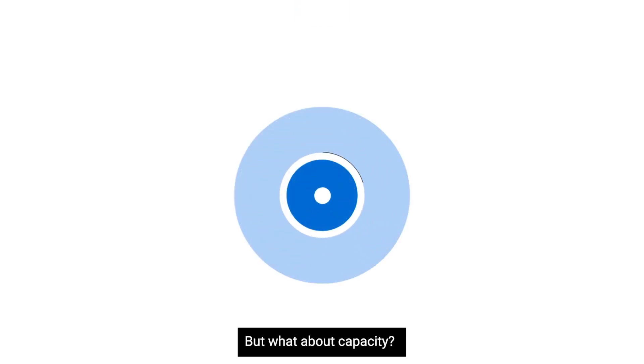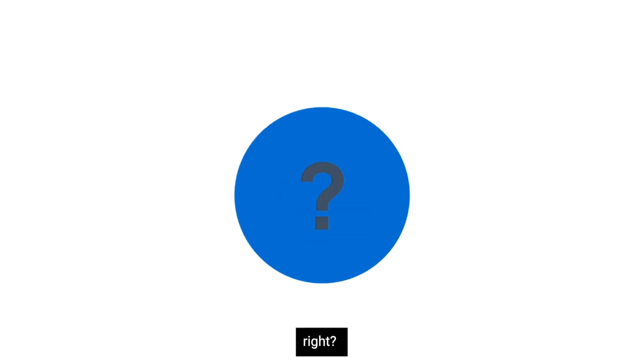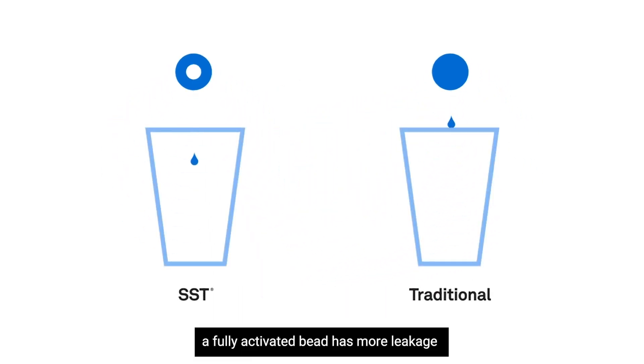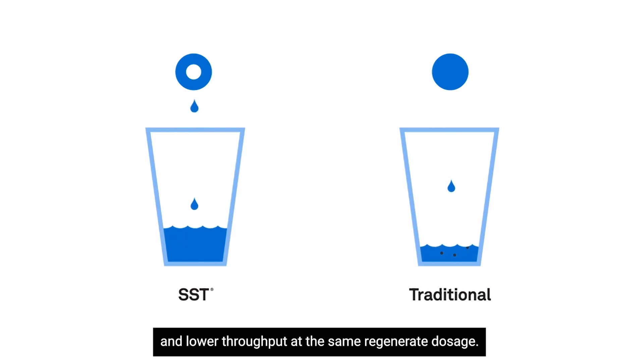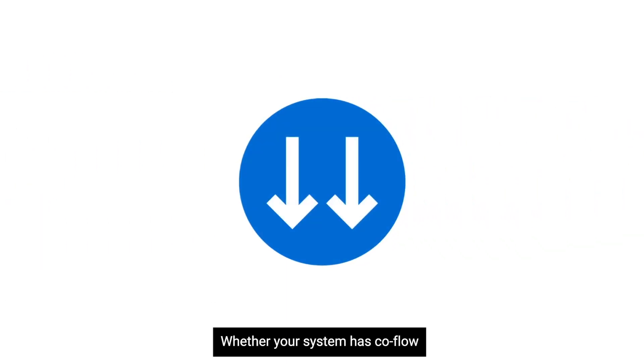But what about capacity? Logically, a bead with more active sites must have more capacity, right? Actually, no. Compared to SST, a fully activated bead has more leakage and lower throughput at the same regenerate dosage.